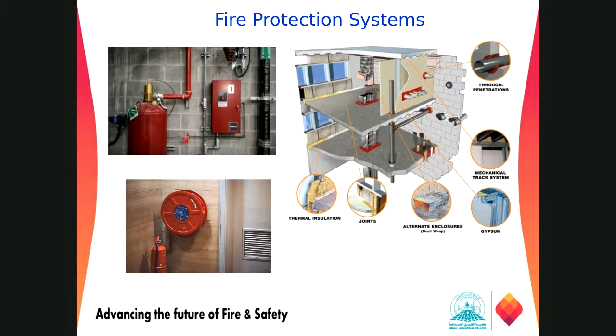In this figure, on the left we have a gaseous suppression system at the top and the bottom. These are some examples of the active fire protection system. On the right, we can see a through penetration. A pipe is just penetrating a wall, and those walls need to be sealed. So this is a passive fire protection system. We have a gypsum board. Gypsum has some fire ratings, the joint, the thermal insulation, and so on. So passive means it is just a construction material to isolate the fire within the same area of origin. The fire should not go outside of those boundaries.